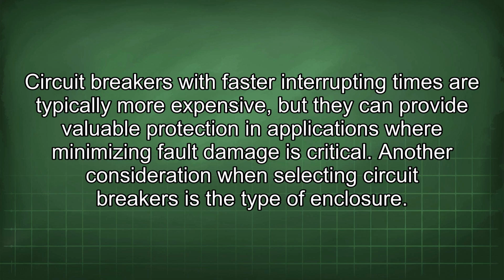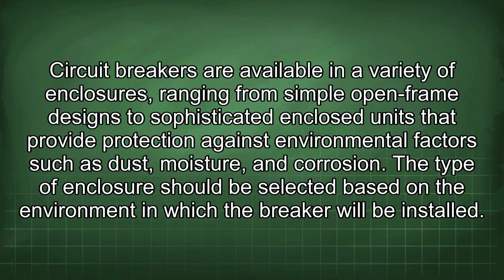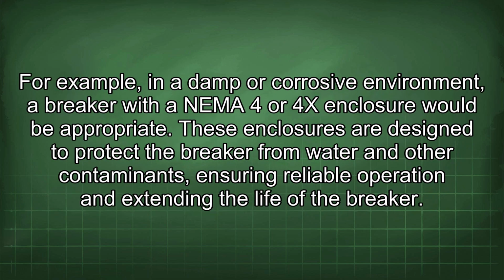Another consideration when selecting circuit breakers is the type of enclosure. Circuit breakers are available in a variety of enclosures, ranging from simple open-frame designs to sophisticated enclosed units that provide protection against environmental factors such as dust, moisture, and corrosion. The type of enclosure should be selected based on the environment in which the breaker will be installed. For example, in a damp or corrosive environment, a breaker with a NEMA 4 or 4X enclosure would be appropriate.